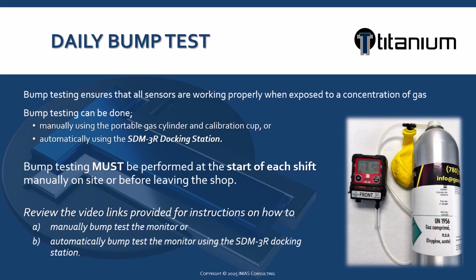Bump testing ensures that all sensors are working properly when exposed to a concentration of gas. Bump testing can be done manually using the portable gas cylinder and calibration cup, or automatically using the SDM-3R docking station. Bump testing must be performed at the start of each shift manually on site, or before leaving the shop. Review the video links provided for instructions on how to manually bump test the monitor or automatically bump test the monitor using the SDM-3R docking station.